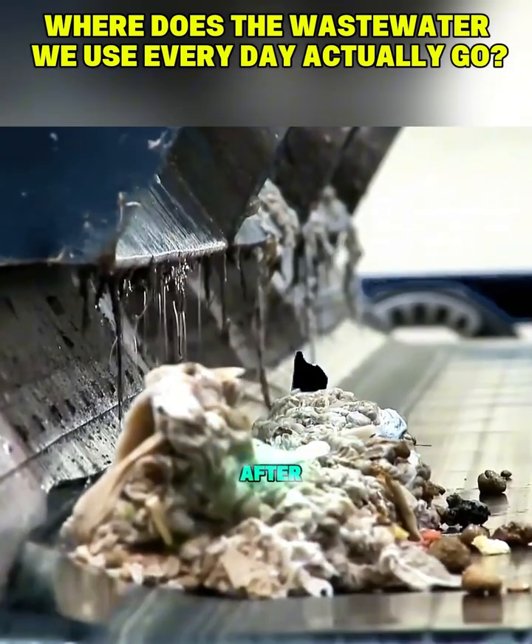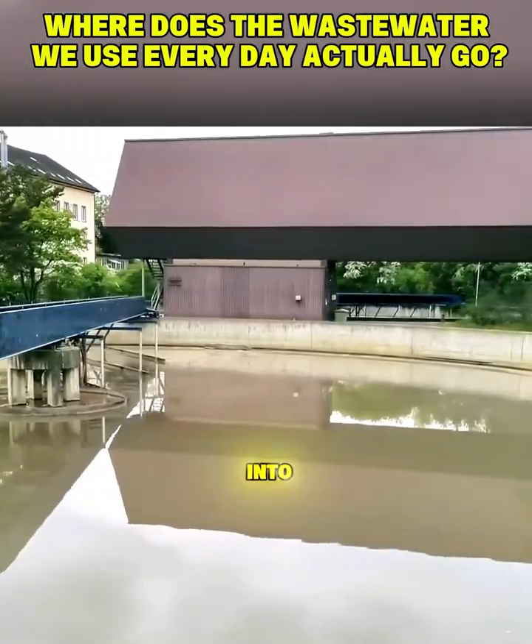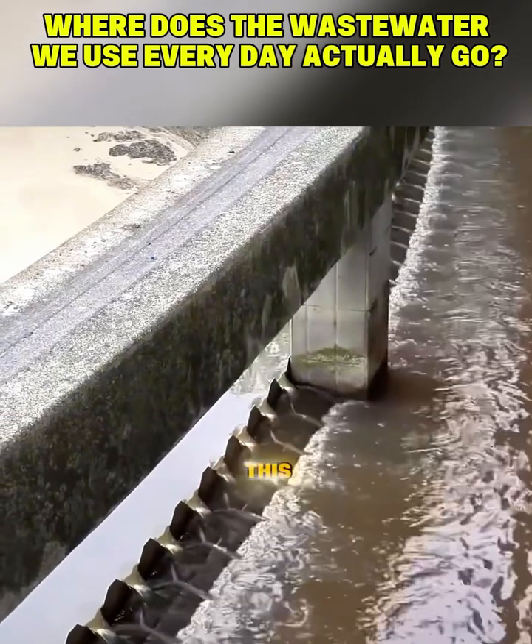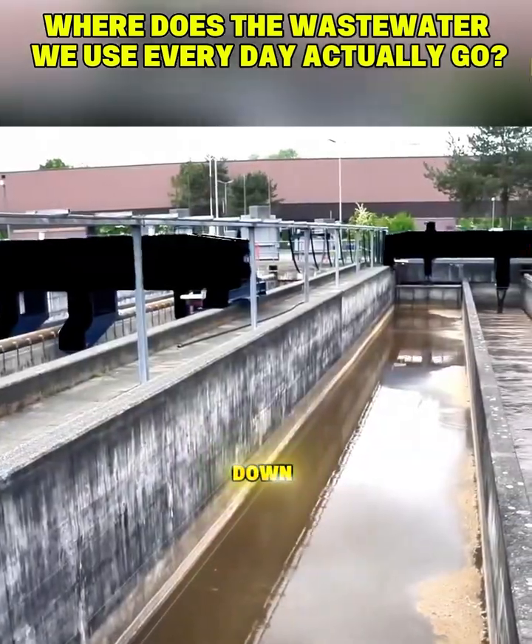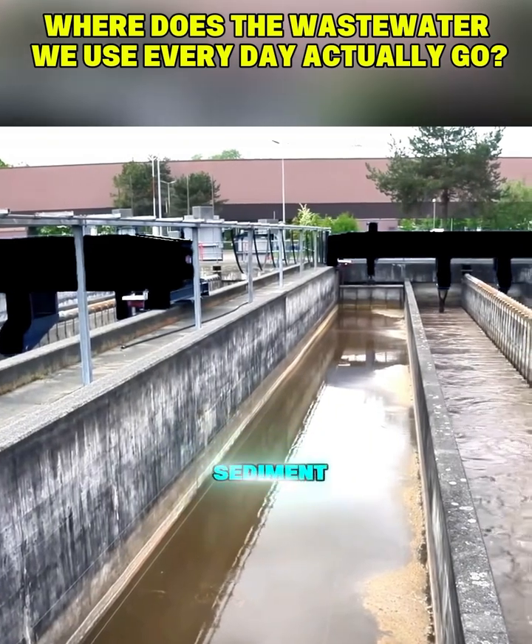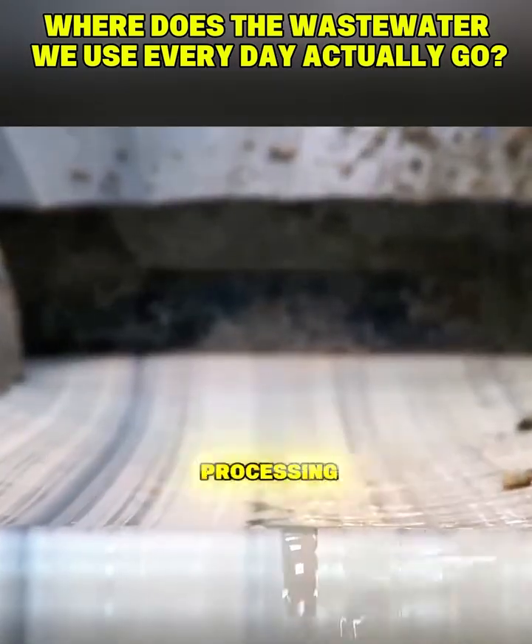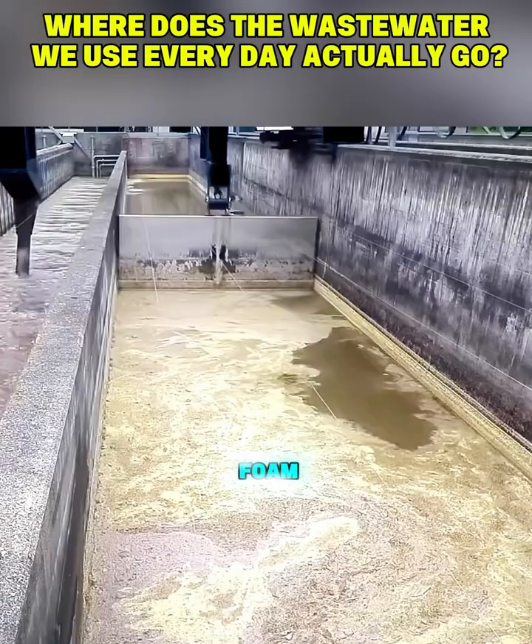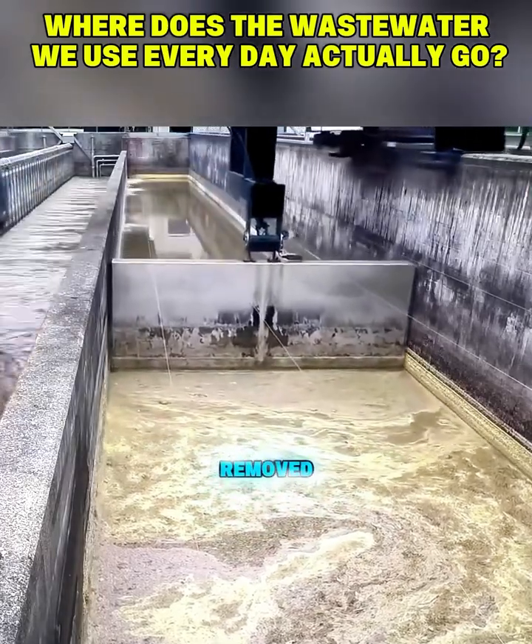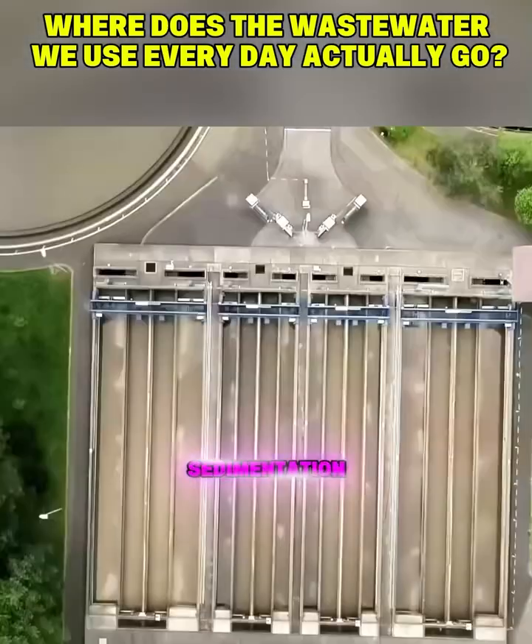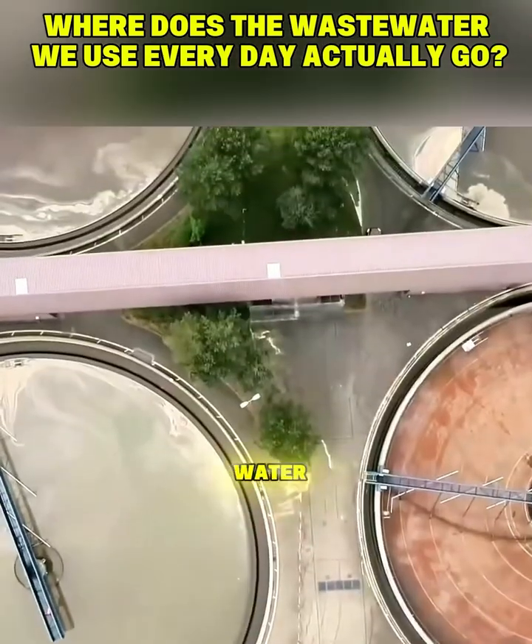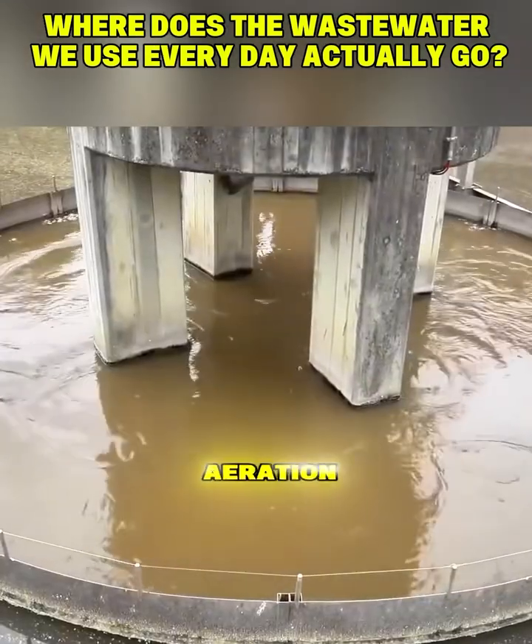The wastewater, after initial filtration, flows into a sedimentation tank. At this point, the water flow slows down, and sediment and particles settle to the bottom. The settled sediment is sucked into a separator for processing, while oils and foam on the water surface are removed. After preliminary sedimentation and oil removal, the wastewater flows through pipes into an aeration tank.